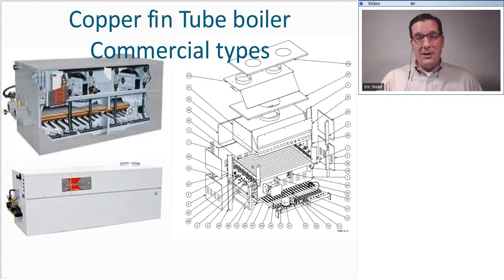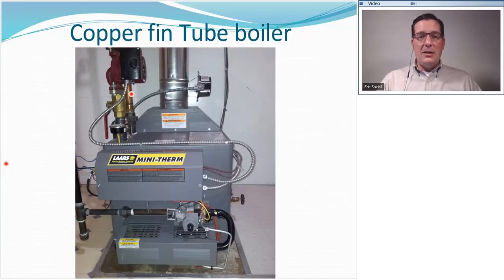Now, that doesn't always necessarily mean it's easy. Sometimes you have to look carefully to figure that out. Now, one additional thing, we'll talk more about this when we talk about circulator pumps, but I want to come back to this: there's always a hump on the pump, and the hump is in the direction of water flow. A lot of pumps will even have an arrow stamped on them, which may or may not be there, or may be visible or may not be visible.